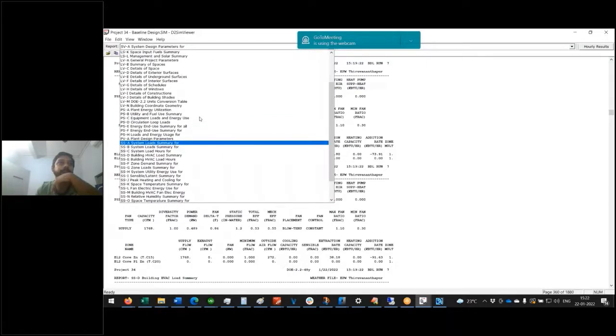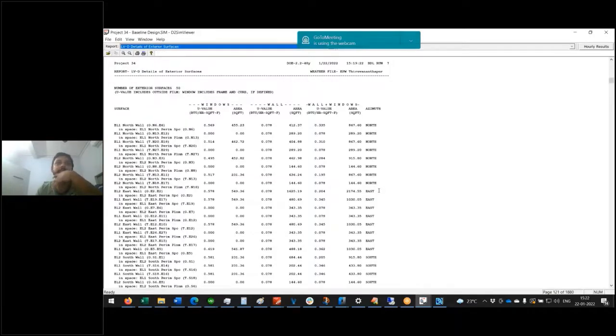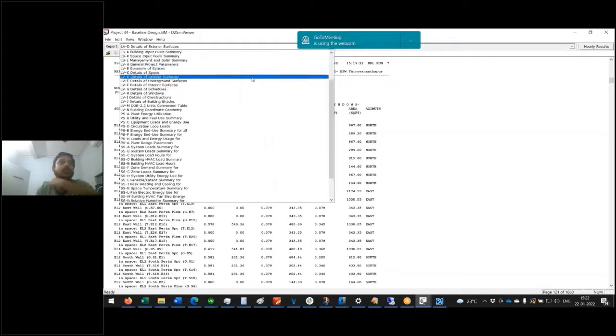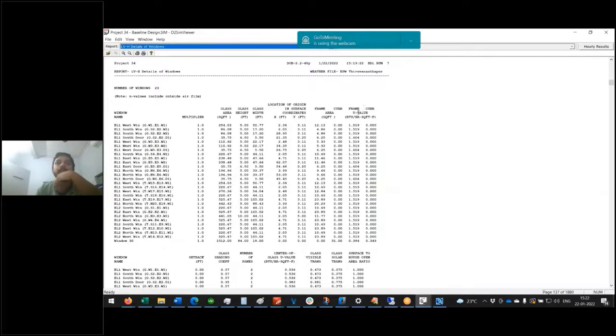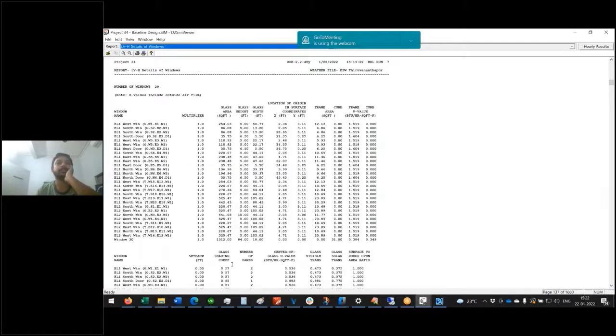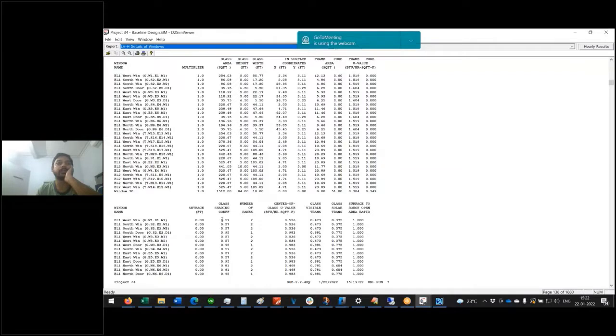So for that, what we'll do is we go to details of exterior surfaces, and here you can see window U value. The SHGC is not here. Let's see, there must be something for the windows. Yeah, details of windows. Frame value. Okay, the shading coefficient. Yeah, the shading coefficient is here. So the main concern for us is the shading coefficient.